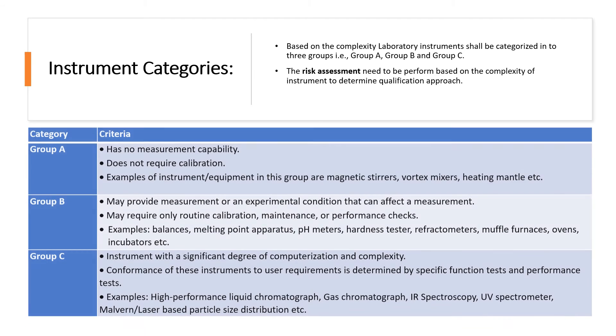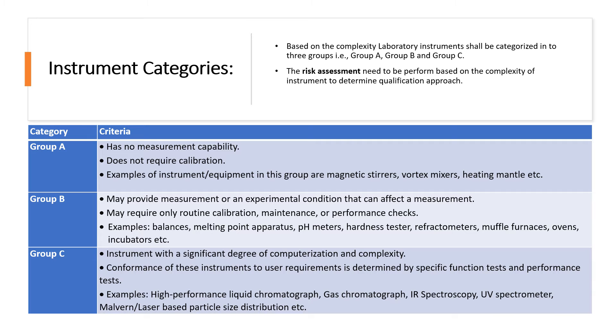Now in this slide, we will discuss the instrument categories. Based on complexity, instruments are categorized into three groups: Group A, Group B, and Group C. Apart from this, a risk assessment also needs to be performed based on the complexity of the instrument to determine the qualification approach. Group A instruments are those which have no measurement capability and do not require any calibration. Examples of Group A instruments include magnetic stirrer, vortex mixer, heating mantle, etc.